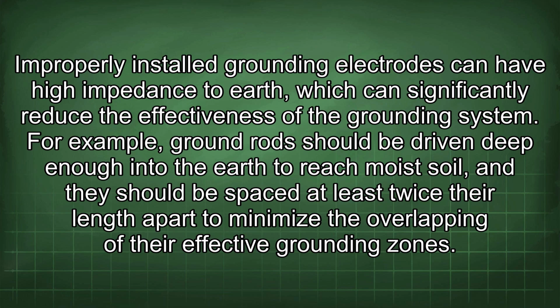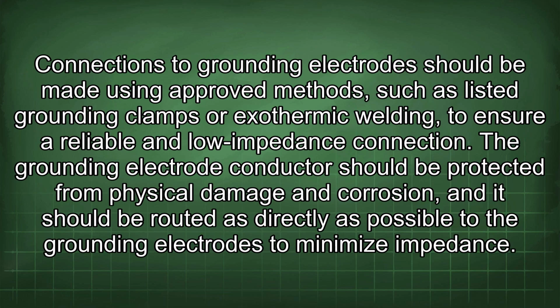For example, ground rods should be driven deep enough into the earth to reach moist soil, and they should be spaced at least twice their length apart to minimize the overlapping of their effective grounding zones. Connections to grounding electrodes should be made using approved methods such as listed grounding clamps or exothermic welding to ensure a reliable and low impedance connection. The grounding electrode conductor should be protected from physical damage and corrosion, and it should be routed as directly as possible to the grounding electrodes to minimize impedance.